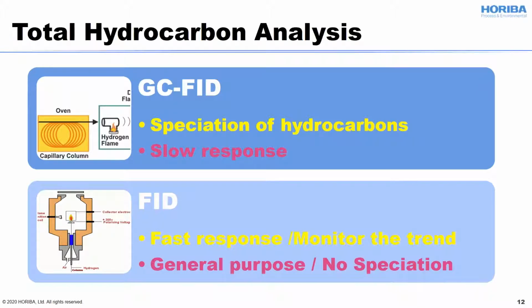Then let's talk about the measurement of hydrocarbons. There are mainly two ways. One is GC-FID and the other is FID. GC-FID is widely used for speciation of hydrocarbons. By using a column, you can identify what hydrocarbons are in the sample and the concentration of each. Because of this column process, GC-FID has a cycle time to complete the measurement. Normal FID does not have that column process, so the sample is fed into the detector directly. This makes a much simpler configuration in the system and gives a fast response. However, because there is no column, you cannot make speciation. So it depends on the purpose. You can choose the right method.